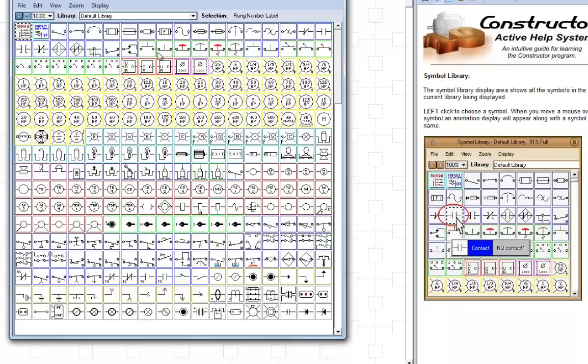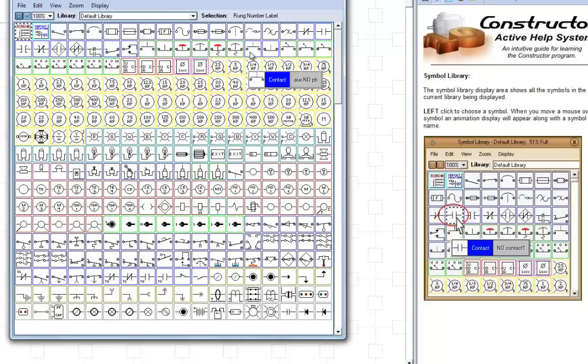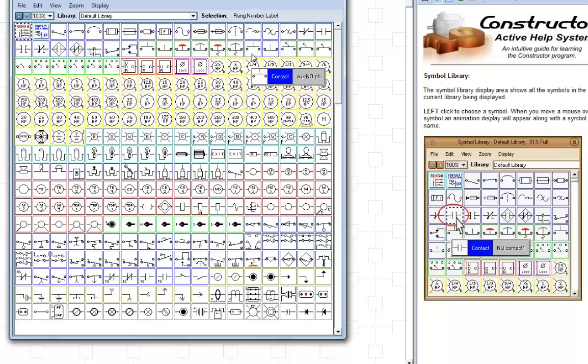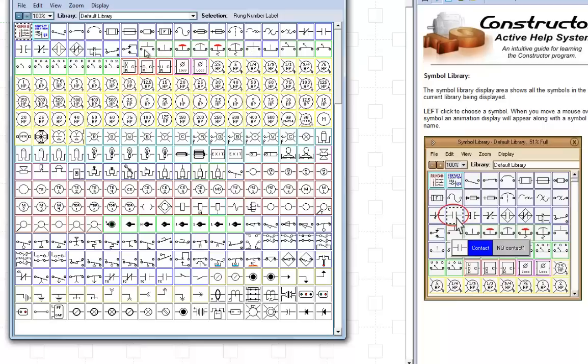These two over here with the dotted lines at the top are auxiliary push buttons. And when you push them, they lock into place because they're meant to be operated by these control head push buttons.